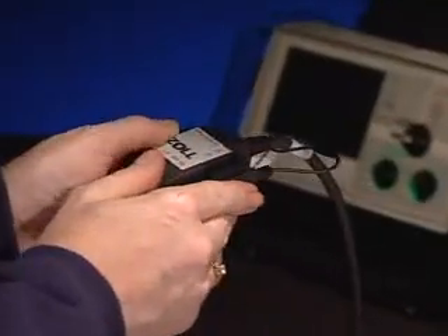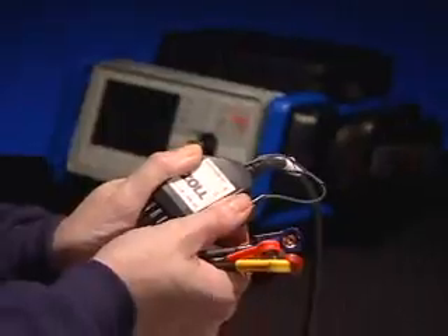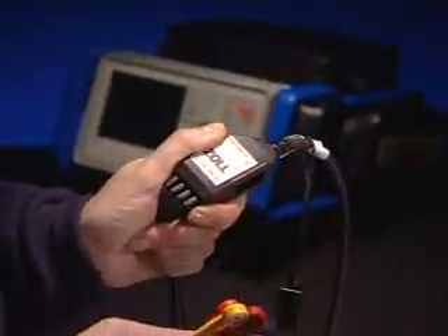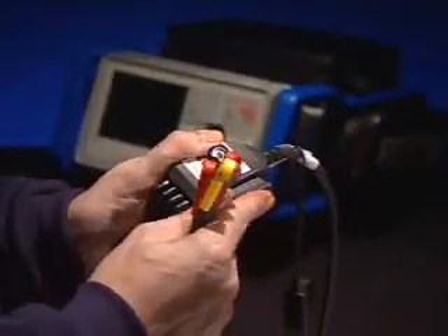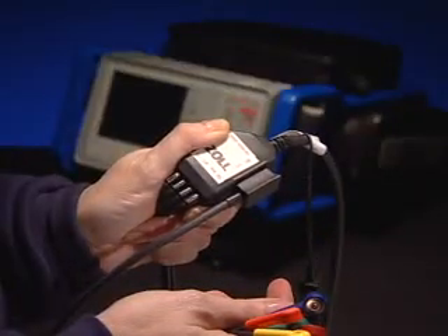When the V-leads are not in use, you must plug the protective cap into the V-lead connector block on the one-step patient cable. When the V-leads are required, remove the protective cap from the connector block and attach the V-lead cable securely into the one-step patient cable slot.